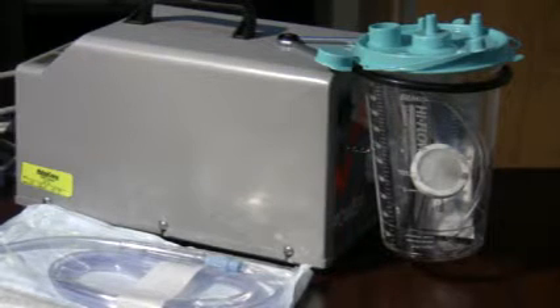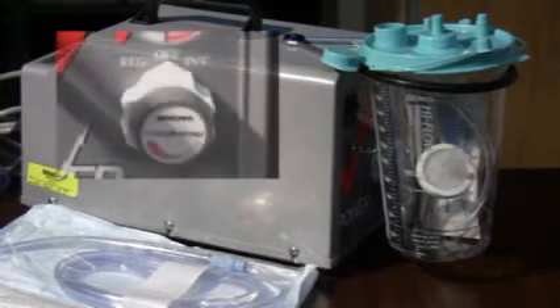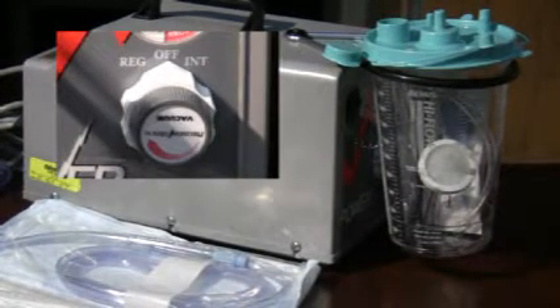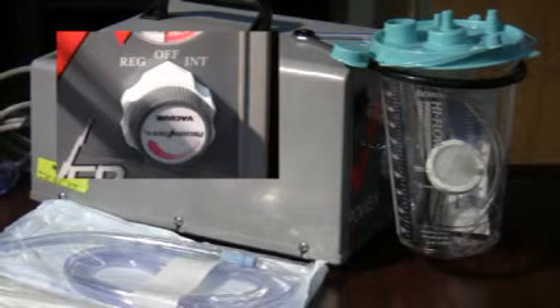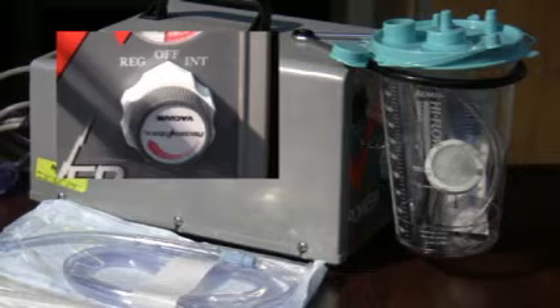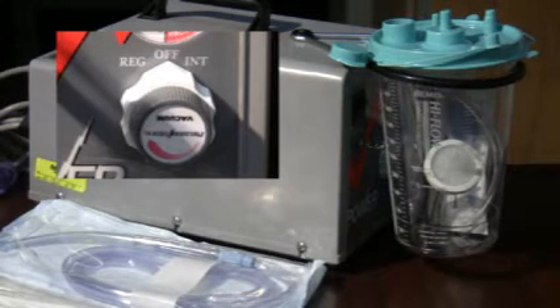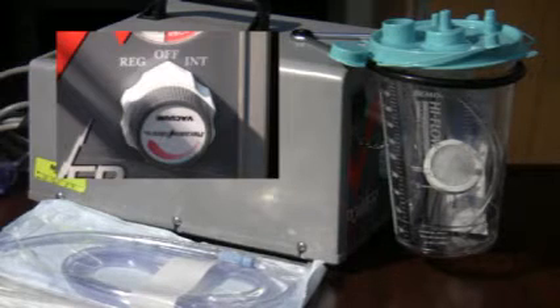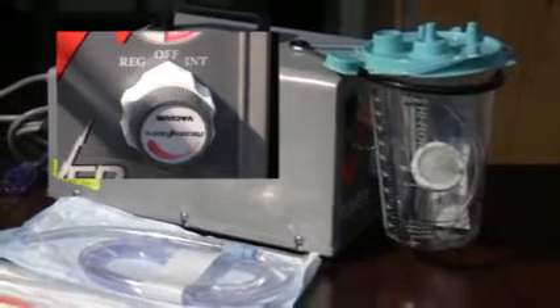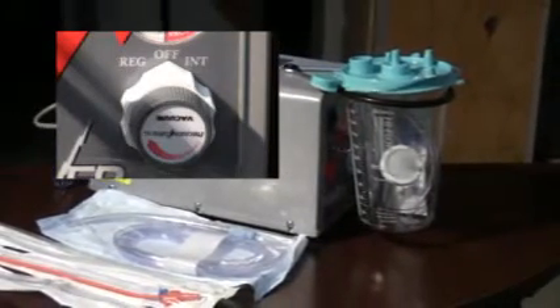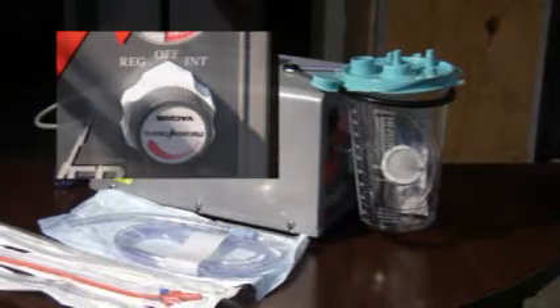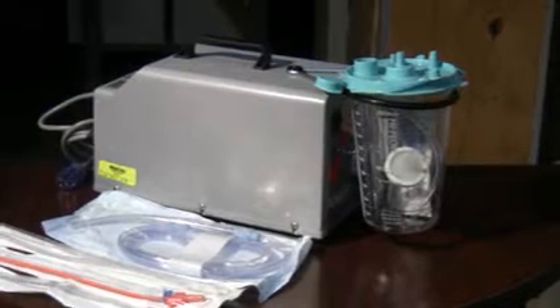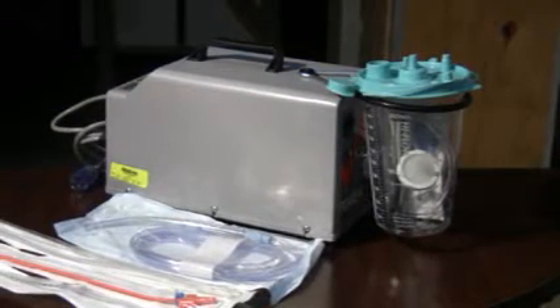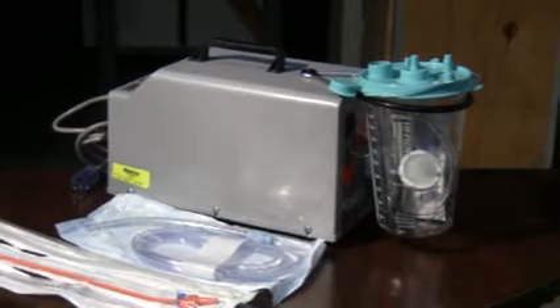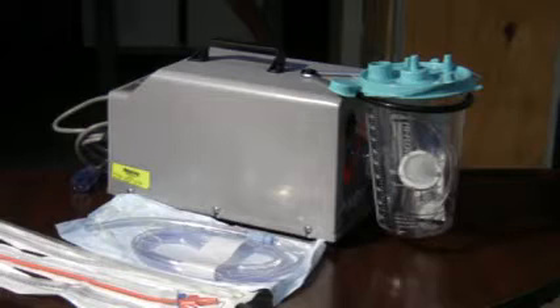It does have 3 different vacuum modes. You do have a reg vacuum mode, which stands for regulated, and provides a continuous vacuum level, which is adjustable. You do have an off vacuum mode, which will provide no vacuum at all during this setting. And then you do have an intermittent vacuum mode, which will provide suction at an intermittent vacuum level, which also is adjustable with vacuum pressure. The intermittent time cycle is factory set at approximately 16 seconds of suctioning time and approximately 8 seconds of off time with no suction. And it will continue in that cycle time.